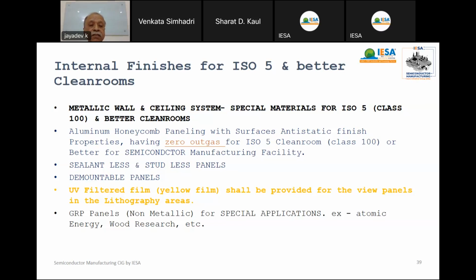Then these panels will be sealantless. Suppose if it is sealant, over a period it may be a contamination. So class 100 requires sealantless and studless. There are no fastenings. Fastenings also may rust or break away. So a better specification of a class 100 clean room is aluminum honeycomb panel with anti-static finish, outgas rate 0, sealantless and studless.